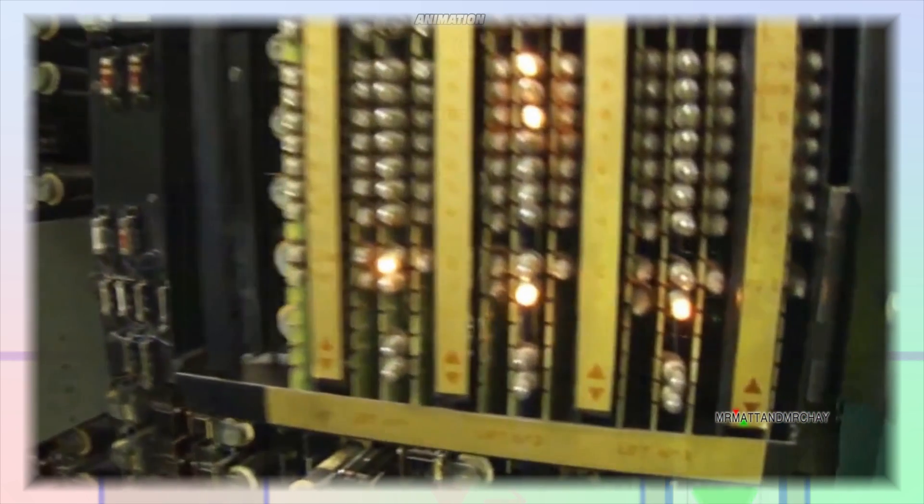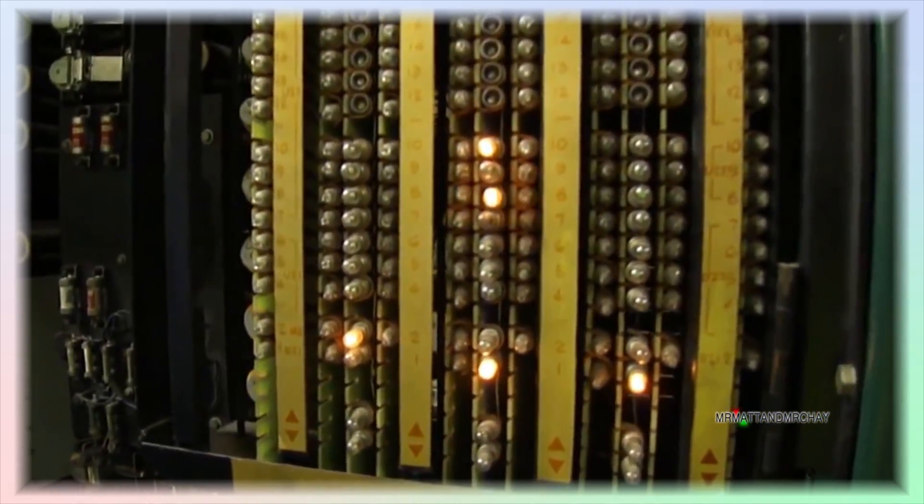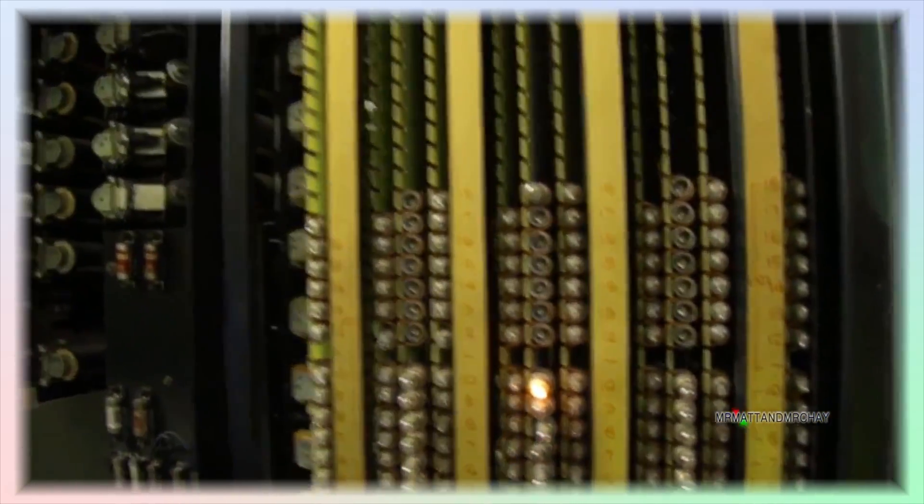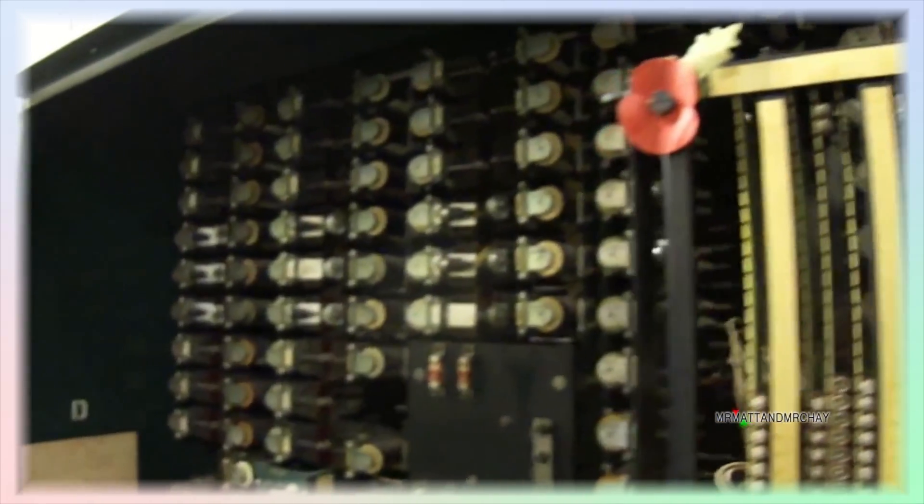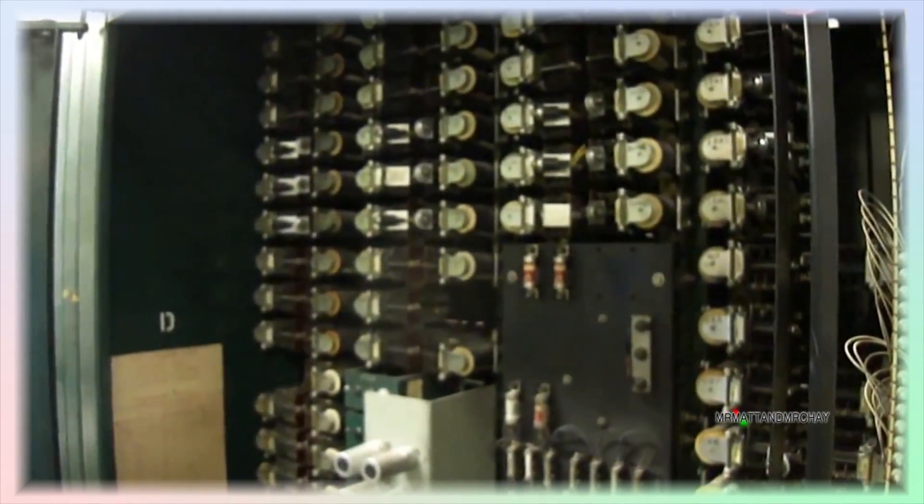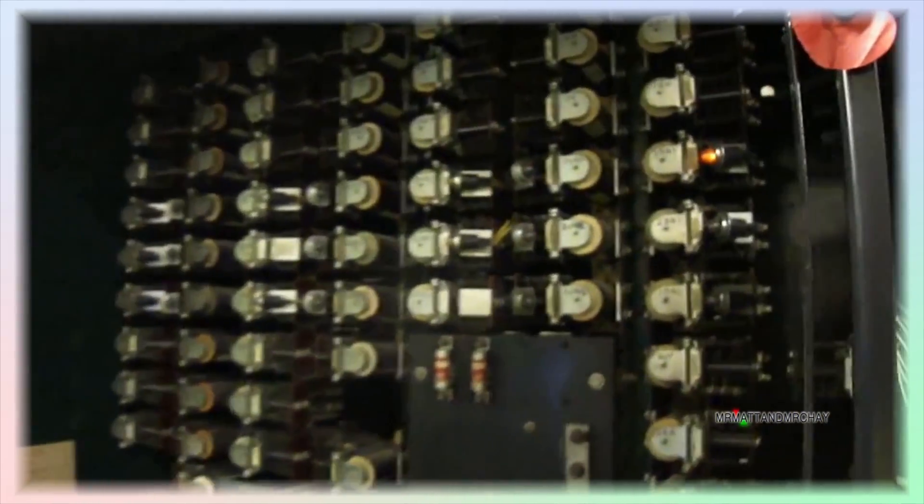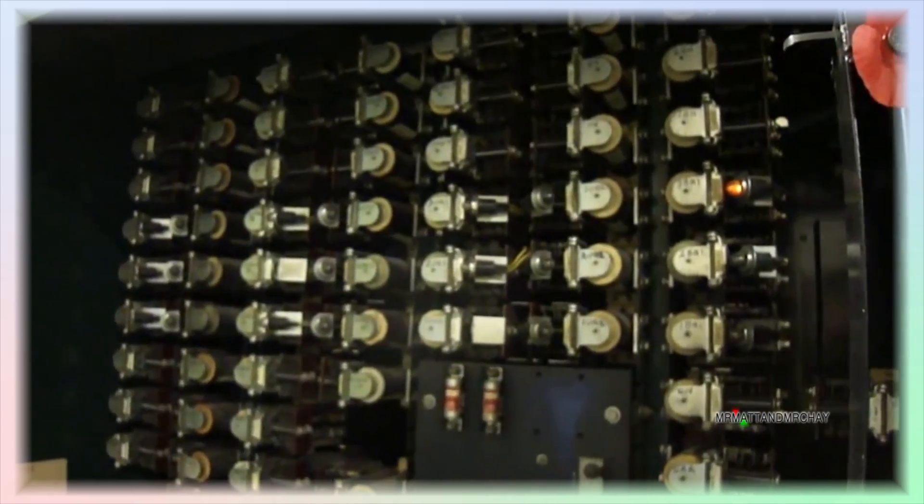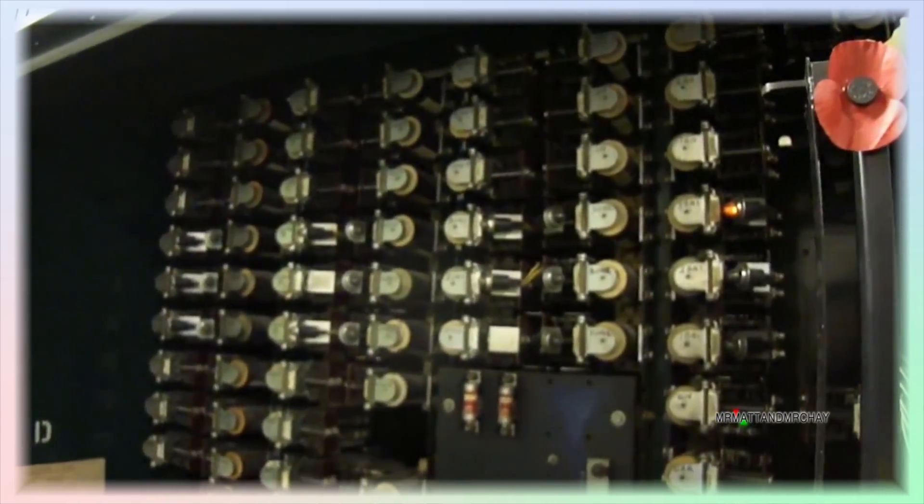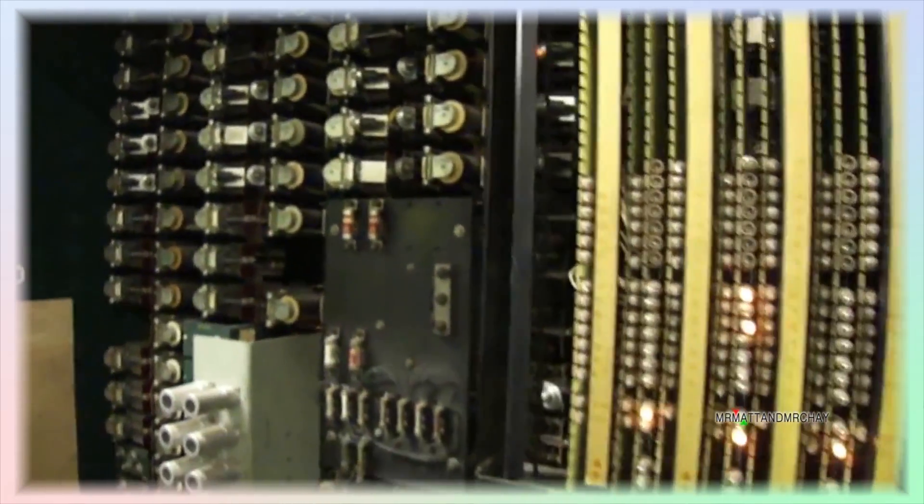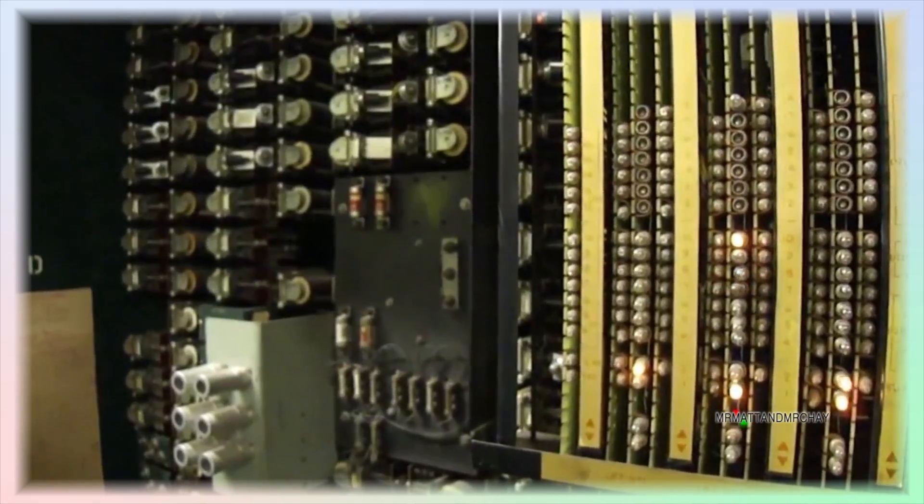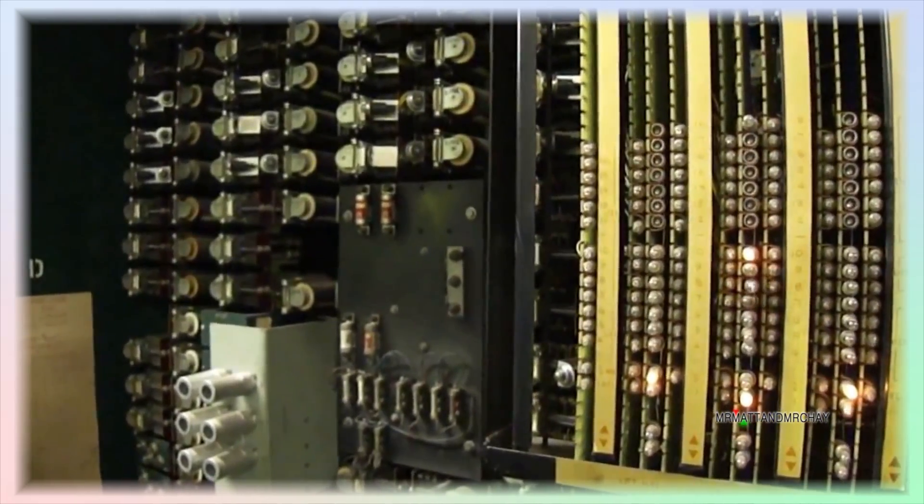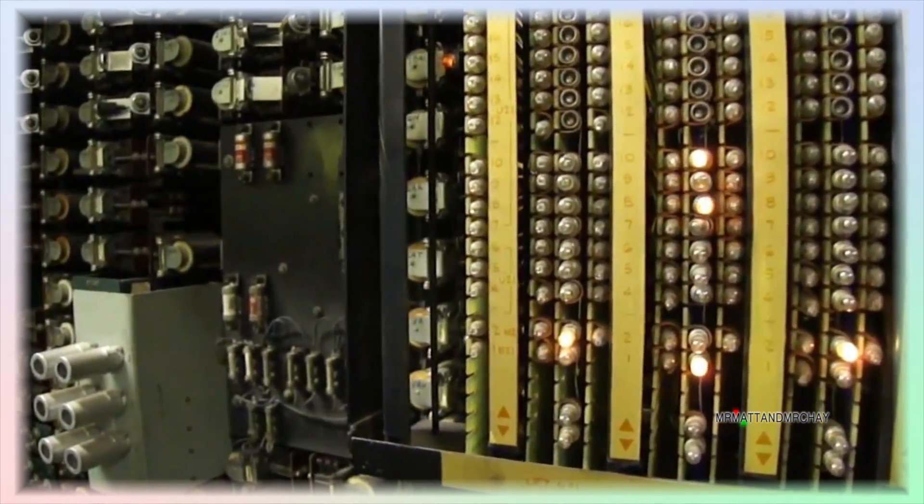See this express DMR system for example. This is an all relay system with far more floors than Hilton Park. This cabinet is called a dispatcher. It controls which lift goes to which floor. There are three lifts in this system. To manage eighteen floors would require a very complex system with hundreds of relays. Instead, floors were divided into groups or sectors.